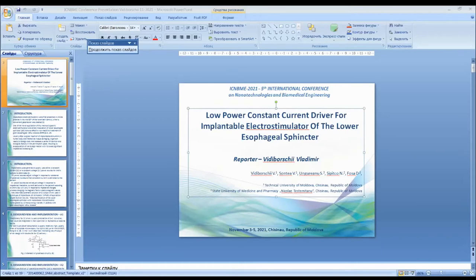At the same time, the traditional stimulators are relatively big devices, and usually they use some batteries to store energy, and have implantable electrodes. Here it gets interesting, because if you have a foreign body in your organism, it begins to react, and this could result in encapsulation and a change in impedance. So that's why implantable stimulators usually use different types of modulation via constant current or constant voltage.